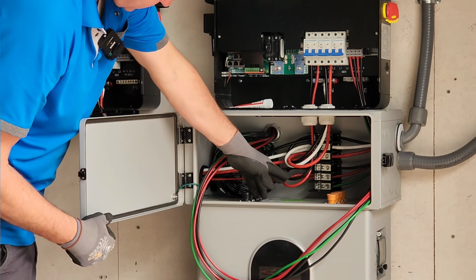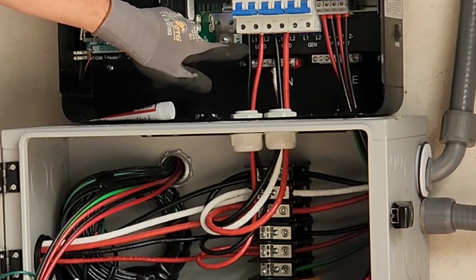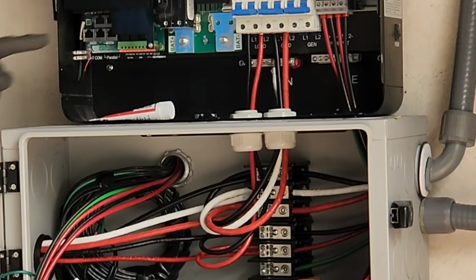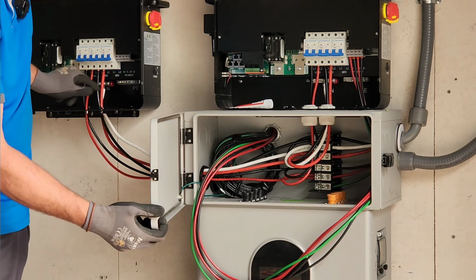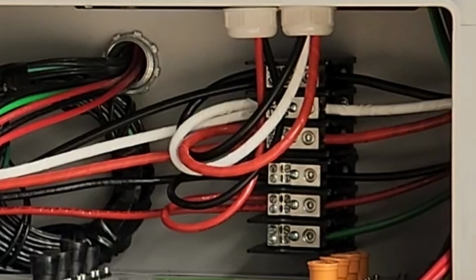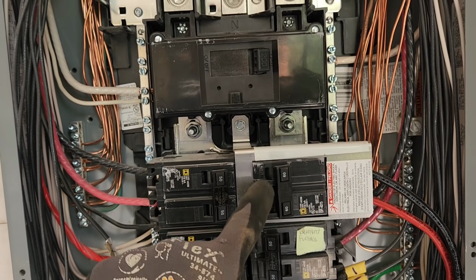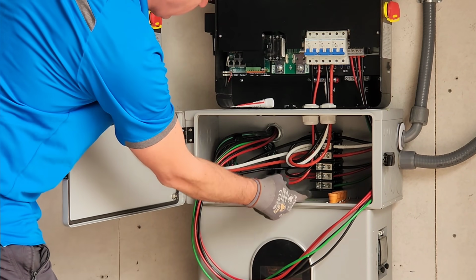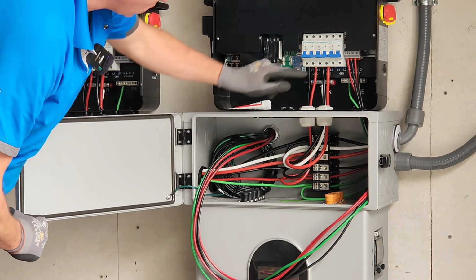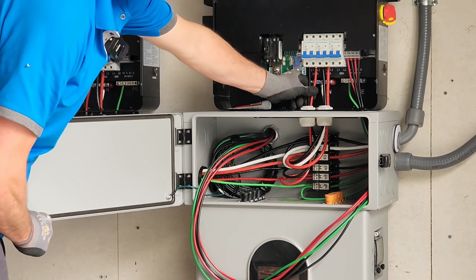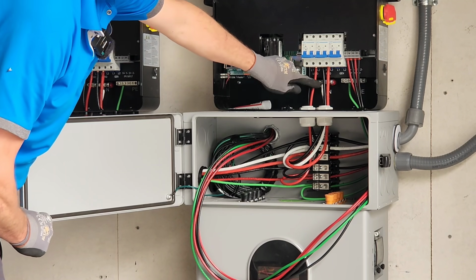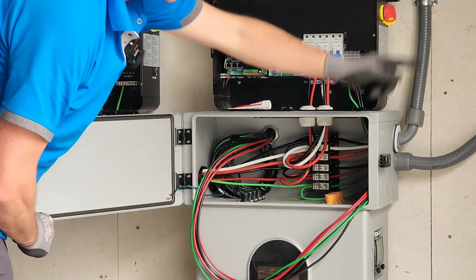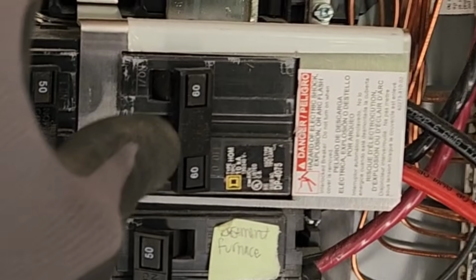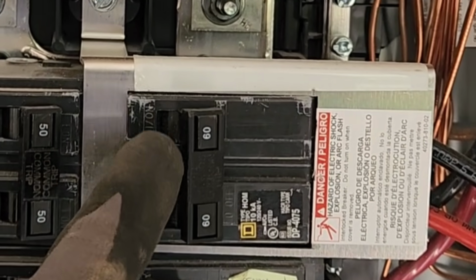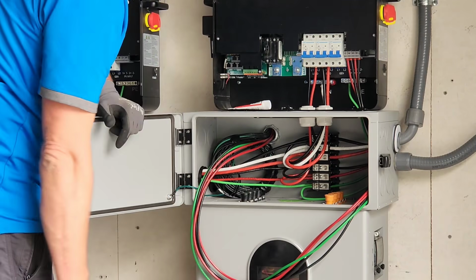Okay, I have everything color coded here. All of my blacks are on L1 and all of my reds are on L2. And that matches between both of these inverters and also on my main electrical panel because that matters. Now I'll just make sure everything is grounded. Now for the load wire, I have 6-gauge wire here, and I believe 6-gauge can accept at least 70 amps, and I've got a 60 amp breaker on my electrical panel, so that wire should be protected.